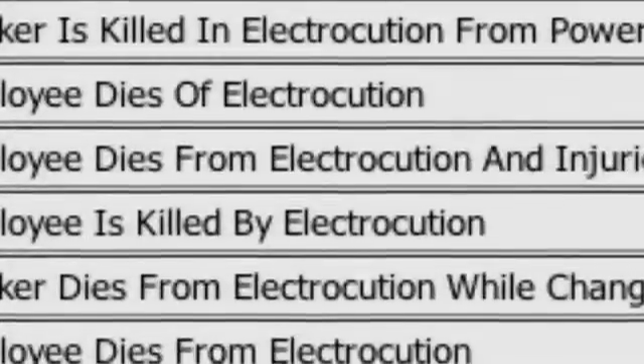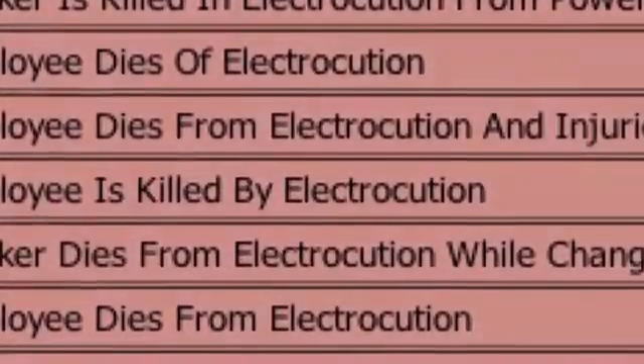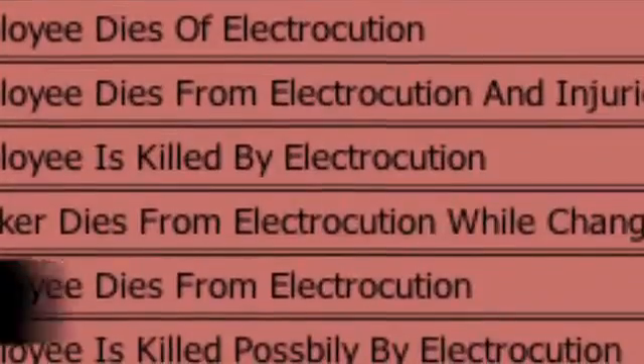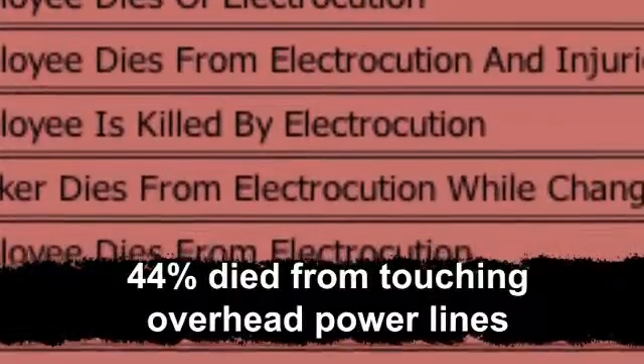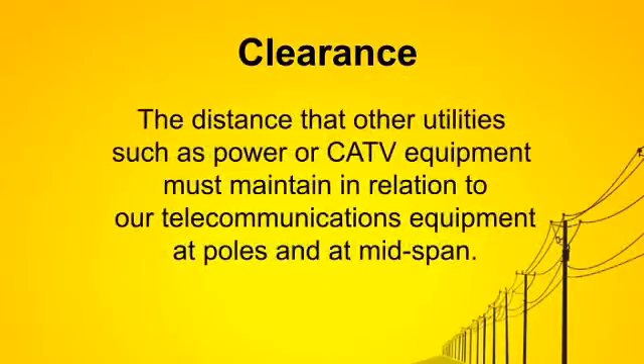Between 1992 and 2010, of the nearly 5,000 people killed by electricity in the United States, 44% died by coming in contact with overhead power lines. You need to know what the proper clearance is, both on poles and at midspan. If the proper clearance does not exist, do not proceed and immediately notify your supervisor or other management. Remember, a clearance is the distance that other utilities, such as power or CATV equipment, must maintain in relation to our telecommunications equipment at poles and at midspan. The distances increase as the voltage increases.